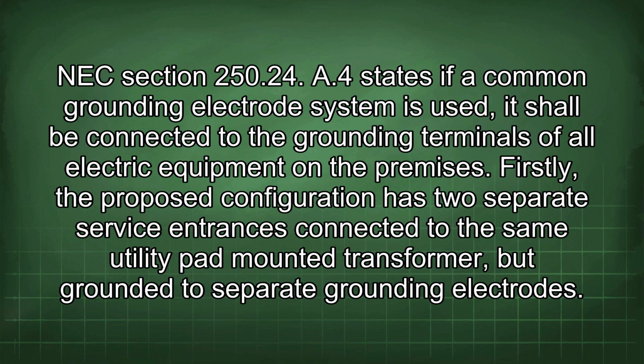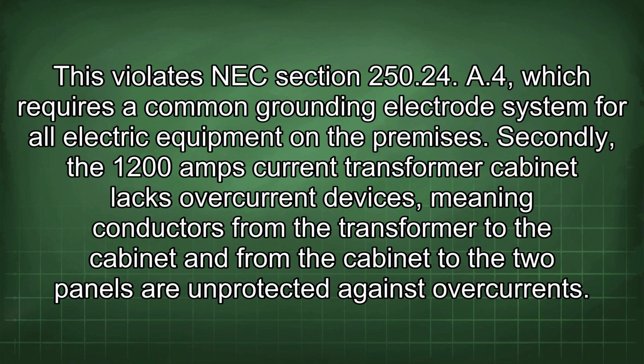Firstly, the proposed configuration has two separate service entrances connected to the same utility pad-mounted transformer, but grounded to separate grounding electrodes. This violates NEC Section 250.24 A4, which requires a common grounding electrode system for all electric equipment on the premises. Secondly, a 1200 amps current transformer cabinet lacks overcurrent devices, meaning conductors from the transformer to the cabinet and from the cabinet to the two panels are unprotected against overcurrents.